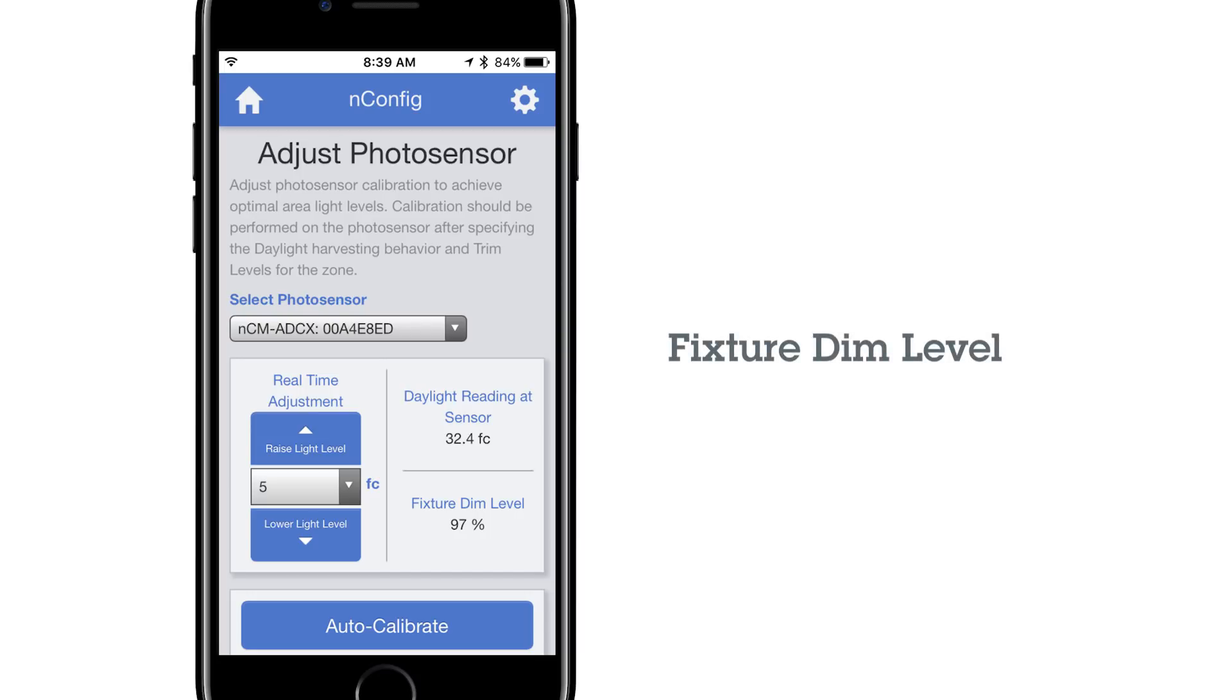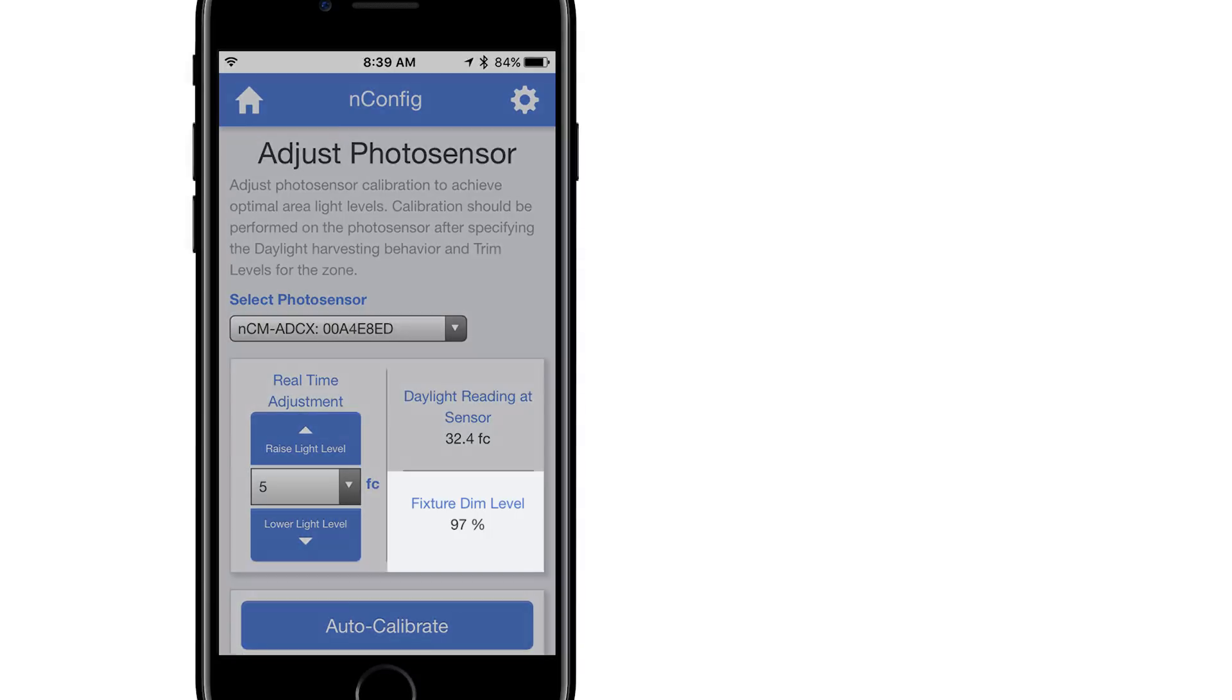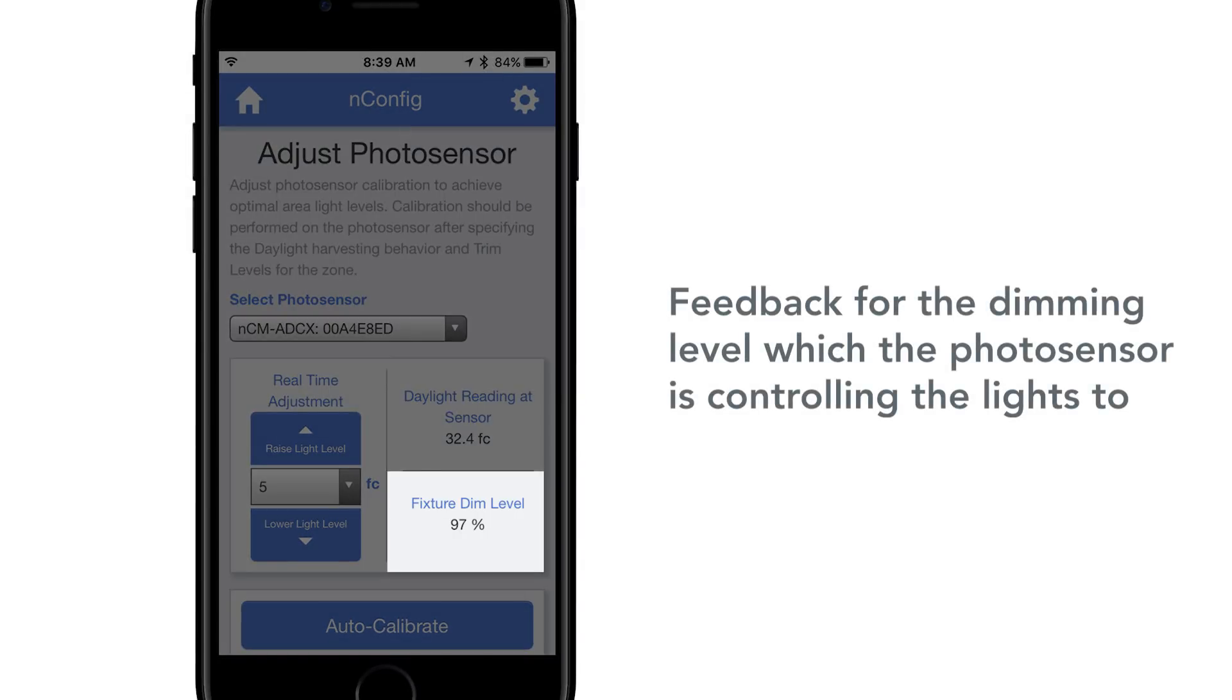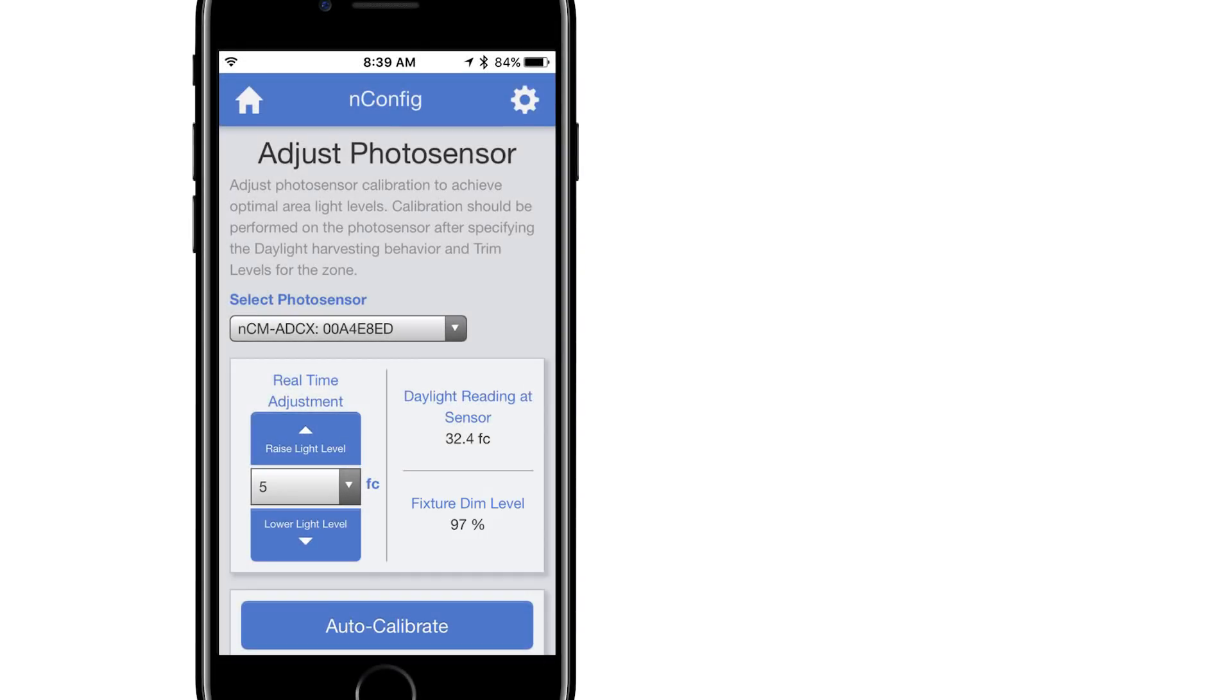Fixture Dim Level. This is live feedback for the dimming level the Photosensor is controlling the lights to. If at 1% or 100%, you have reached the low-high limit of the Photosensor.